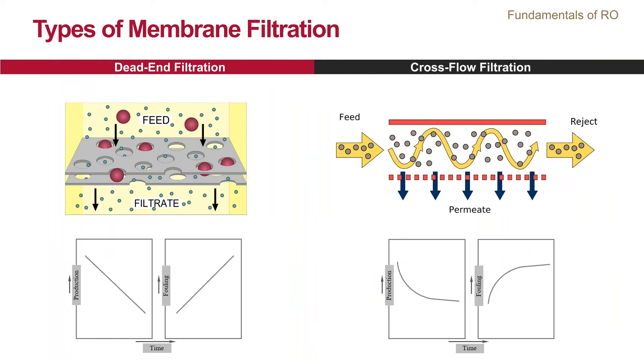There are two major types of filtration: dead-end or direct flow, and cross-flow. In dead-end filtration, all of the feed water passes through the membrane, leaving the solids behind on the membrane. It is a batch process — the filtration system needs to be taken offline and the filter needs to be either cleaned or replaced.